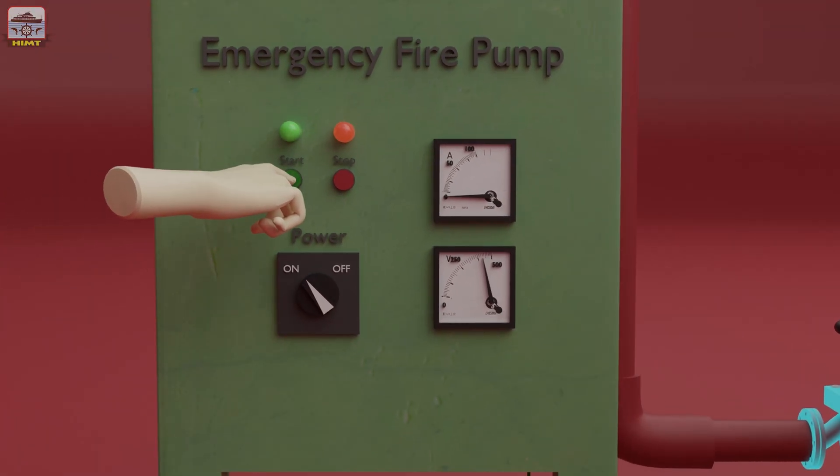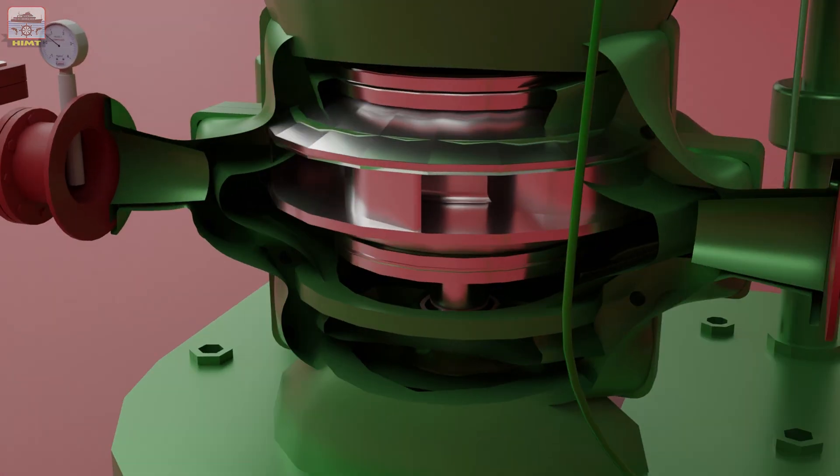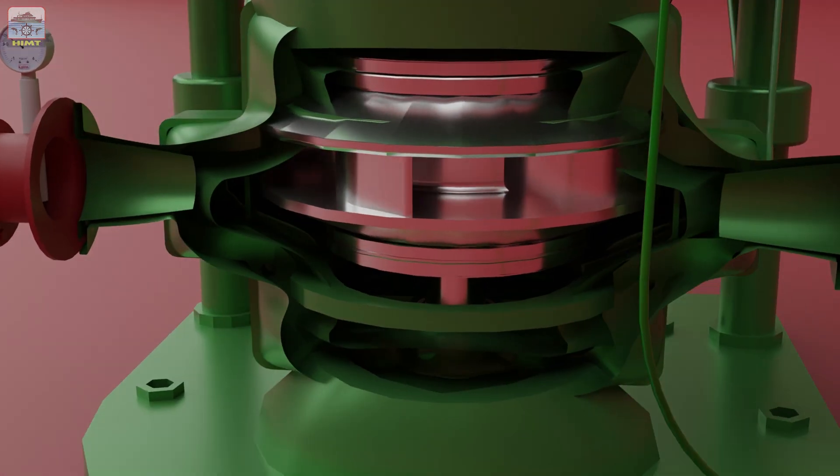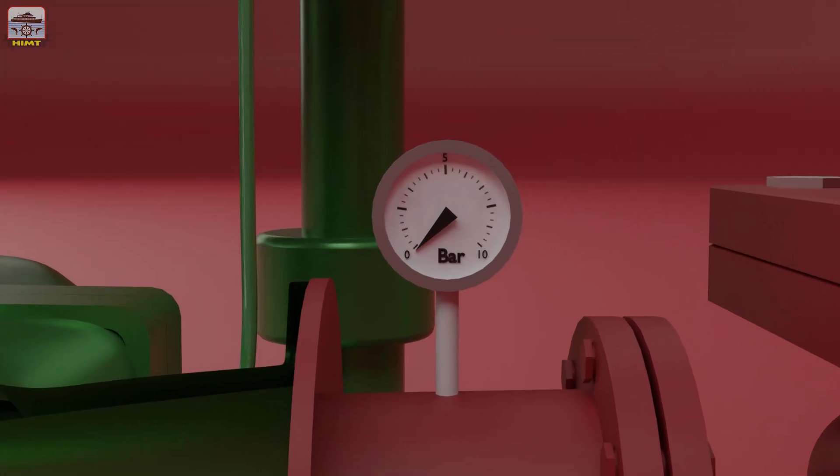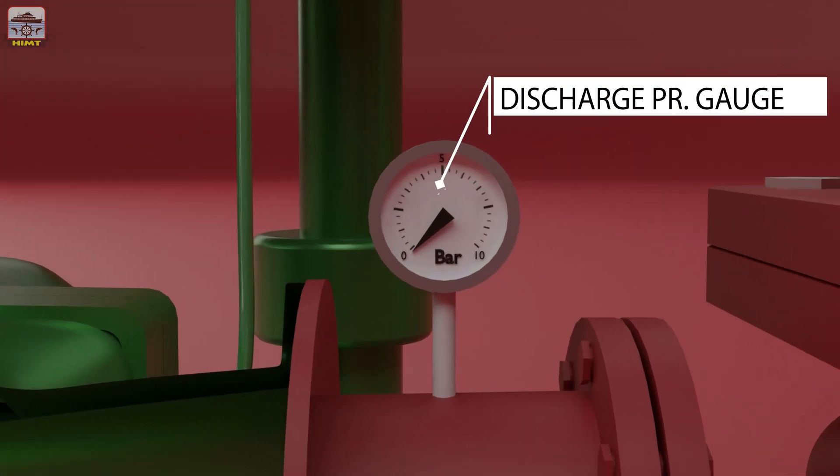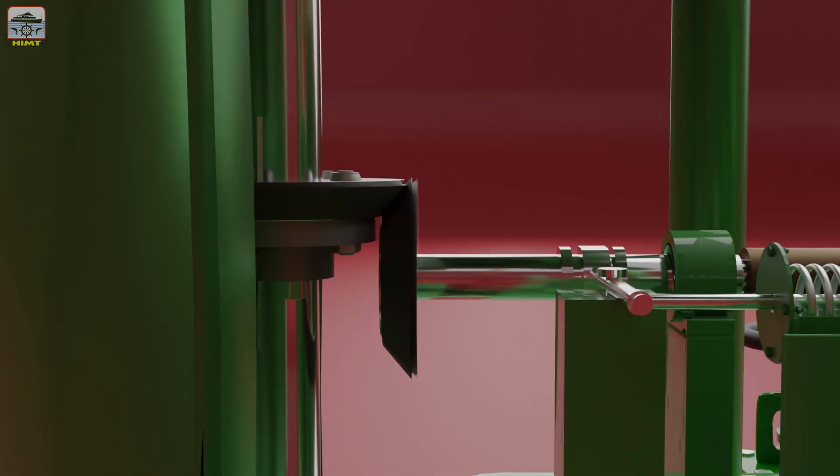When the main pump is started, as there is no water inside the centrifugal pump initially, the pump is not developing the discharge pressure. The auto cylinder keeps the primer pump shaft engaged with the motor shaft.